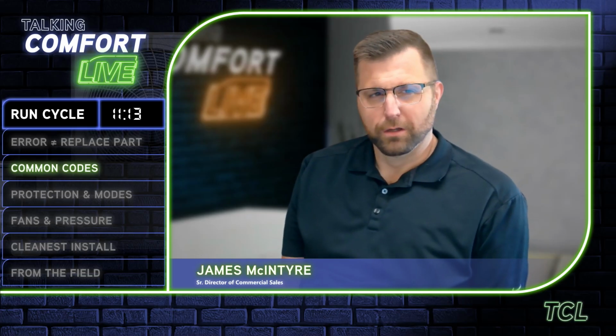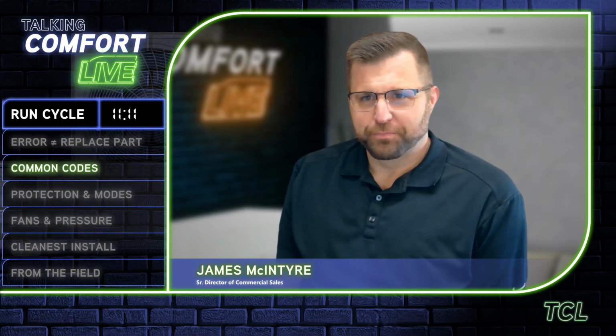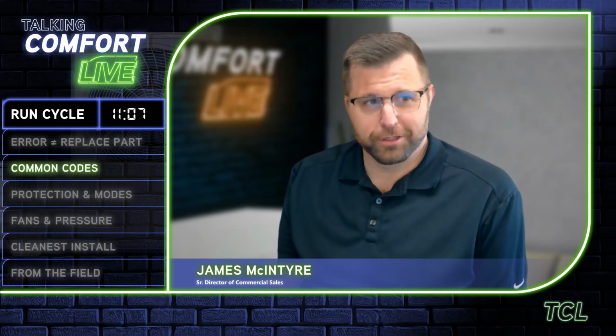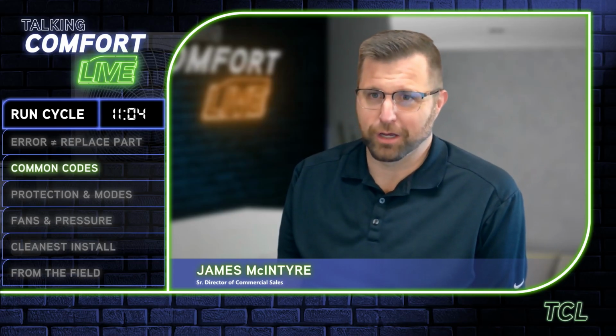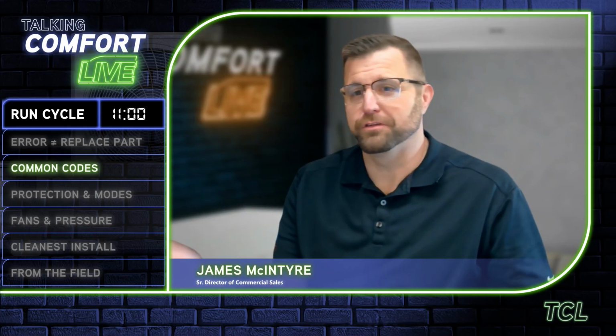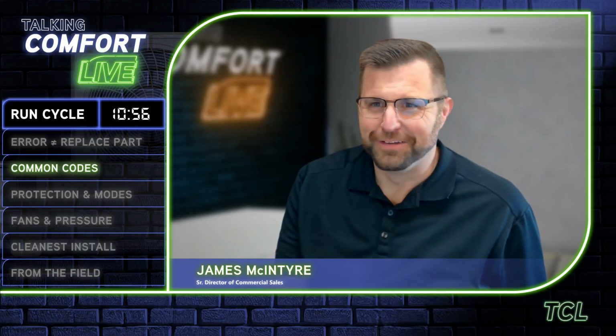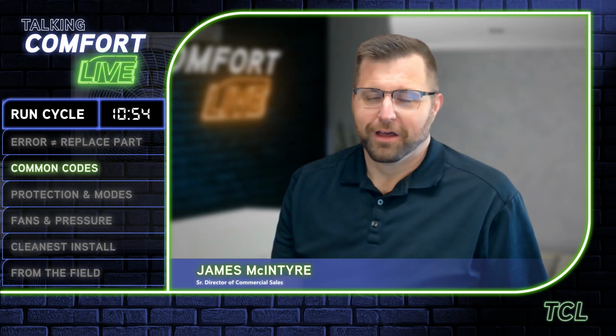We're talking about some real folks writing it, not some engineer somewhere. The instructions in the app that we wrote, and on our website. Literally one of the first steps is, does it have a condensate pump? Everything was working fine. All of a sudden, we get this error code. Well, what could it be? Well, I just installed a condensate pump.